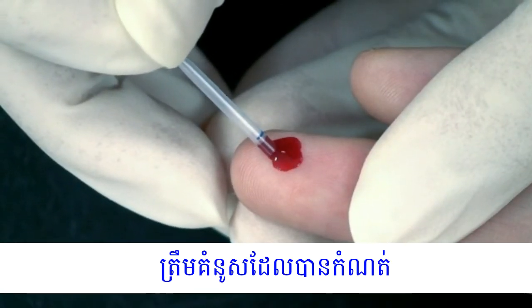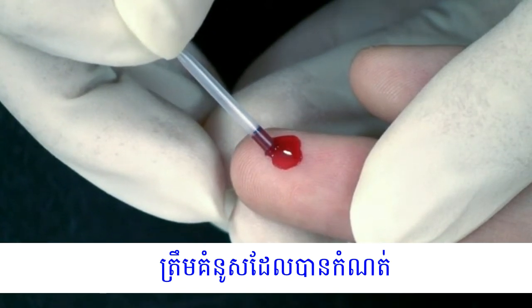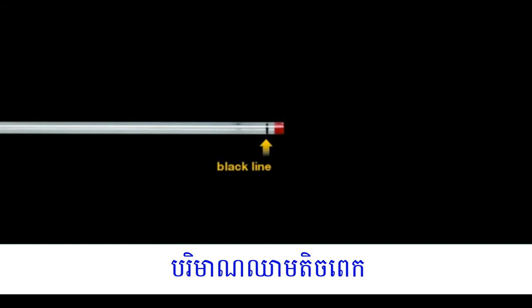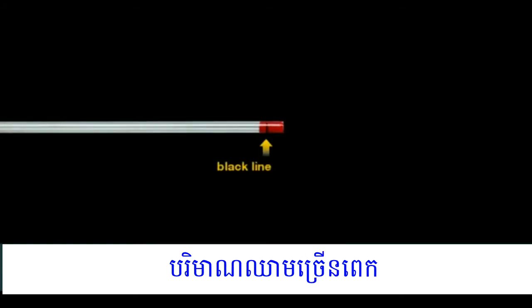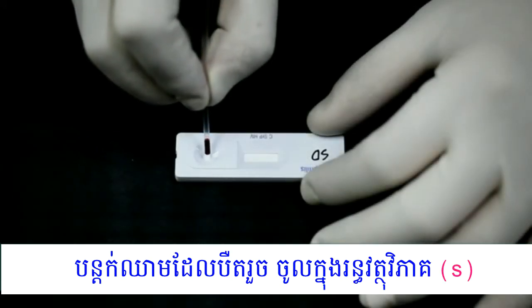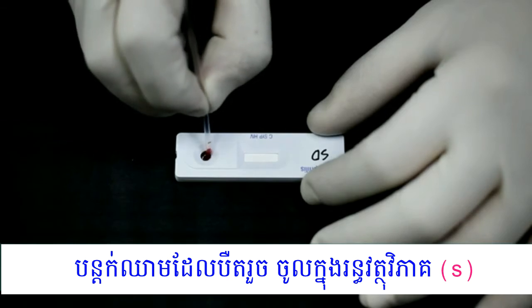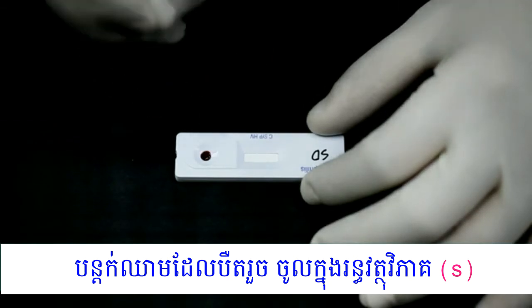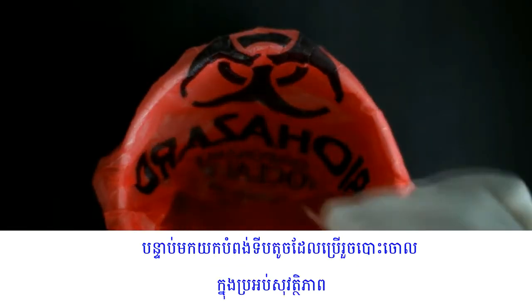The amount of blood collected is critical. This is the correct amount of blood — it is too little if under-filled, and too much if over-filled. Add 20 µL of drawn blood into the round sample well. Discard the capillary pipette immediately in the sharps box.